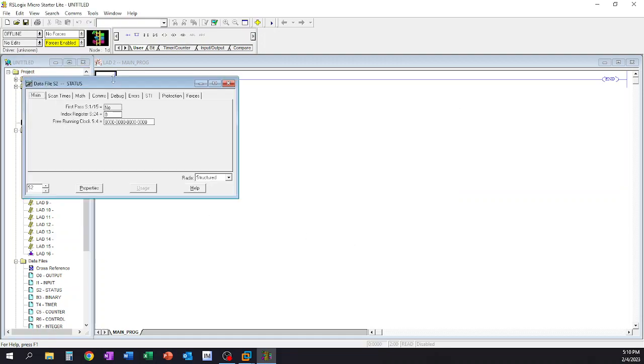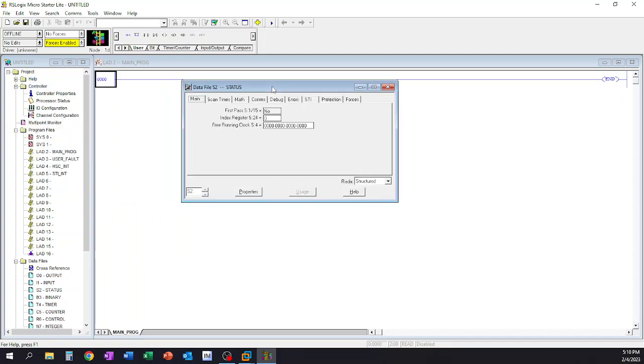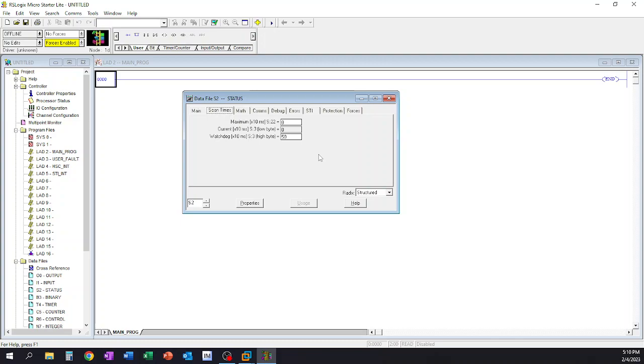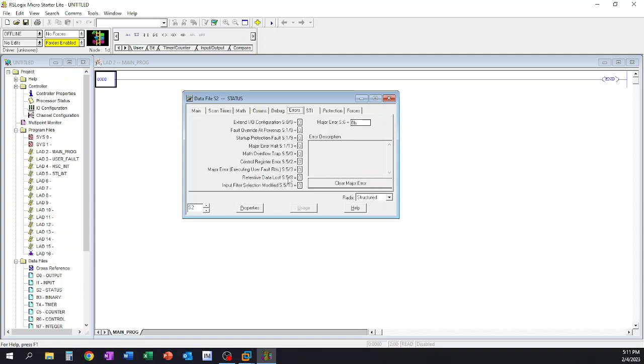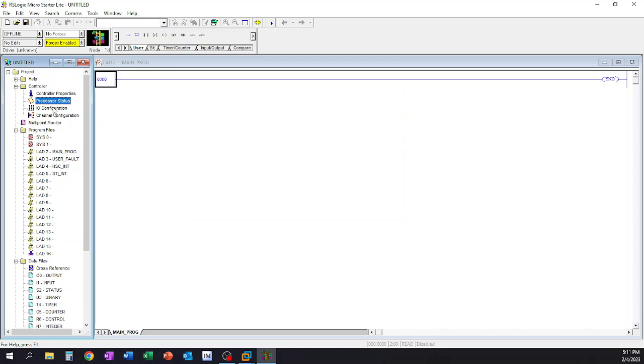Processor status. Now this is kind of important and critical to those that are doing a lot more troubleshooting out on maybe a factory floor or wherever that might be. You'd need to know some of your maybe your scan time of how fast you're scanning. In our case, everything's at zero because we've not actually put this into a processor yet. If you had maybe an overflow type of issue or you wanted to set an overflow trap because your math is adding up beyond the 32,000 number that RSLogix 500 supports, you would catch that here. It continues to go through this. You might have to check your errors file, just kind of depends on what you're looking for in your status, but that's generally what you're going to find in your processor status tab that's underneath your controller folder.